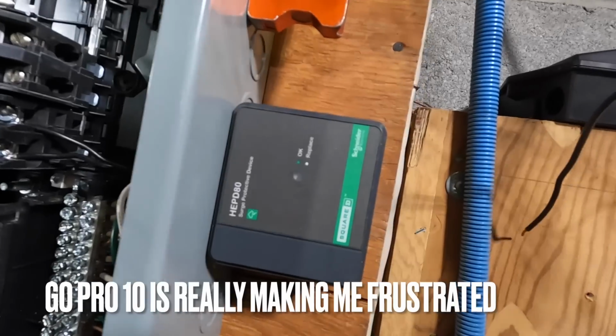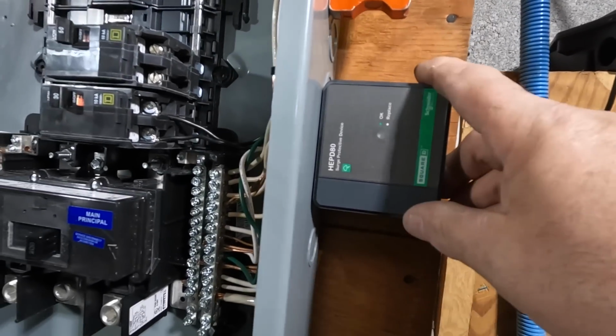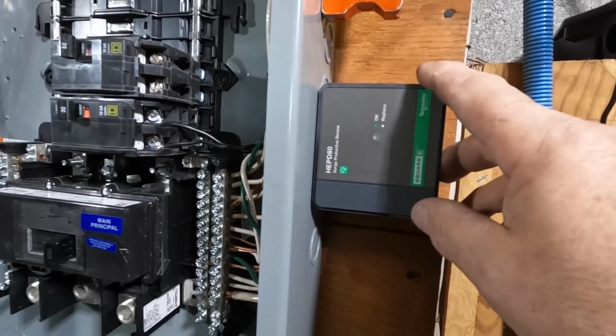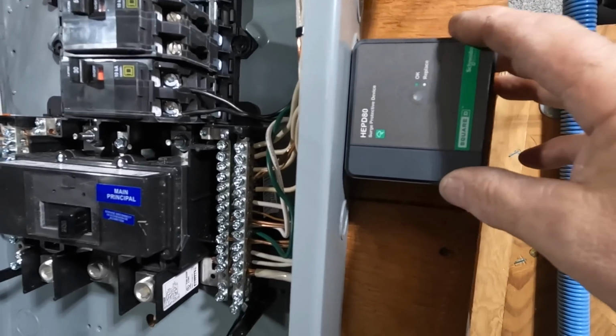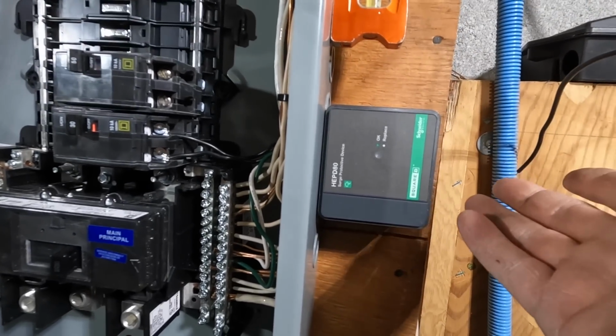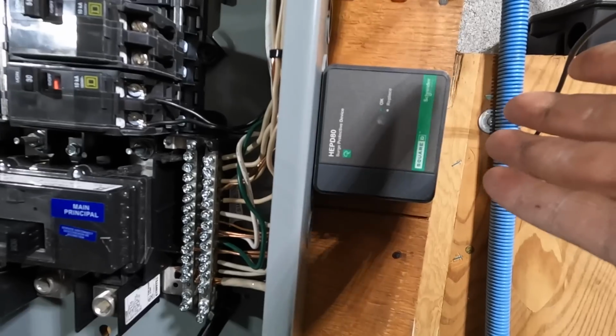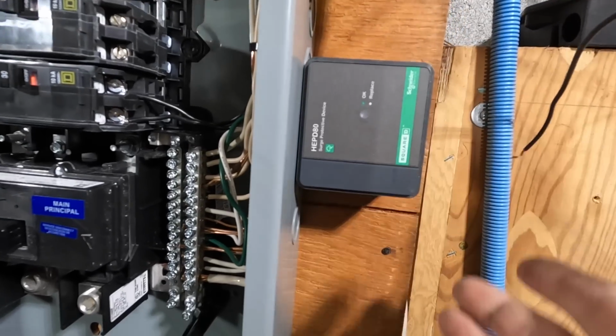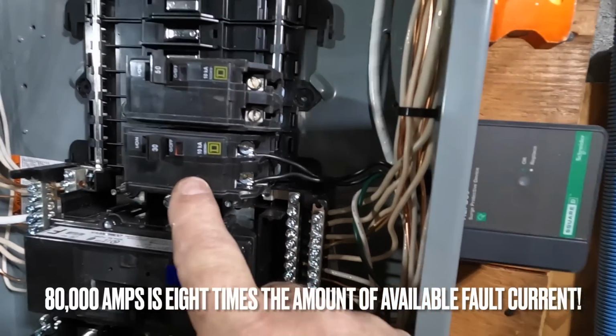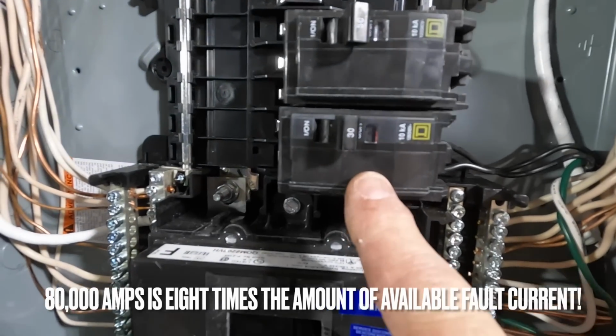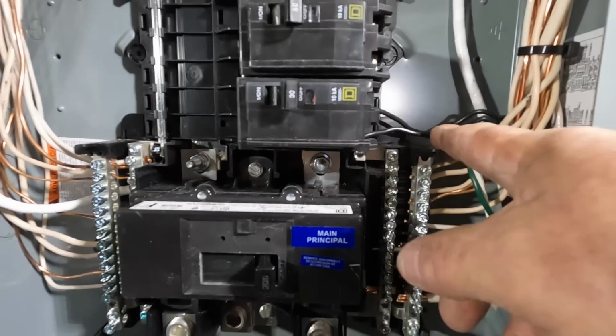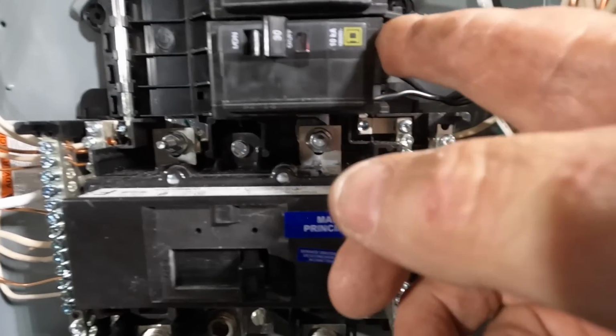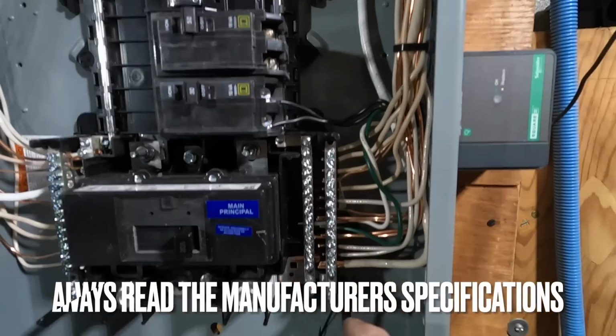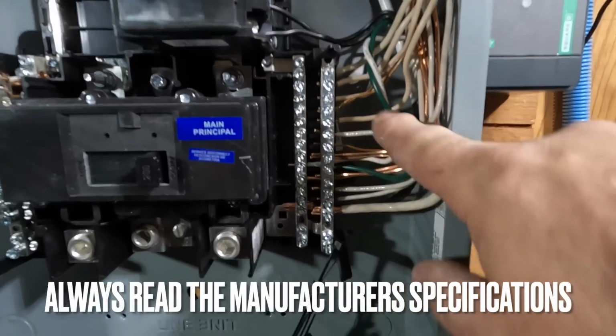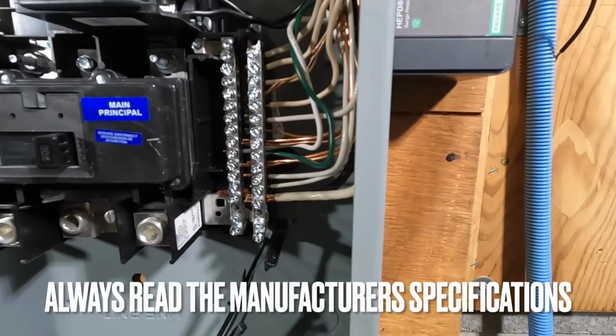So what I did was I added this whole house surge protection device. This is the 80 kiloamp version. This is the joule rating. I'm not exactly sure of this, but this is like the highest rated, best surge protection Square D QO offers. I guess you could hook this up to Homeline as well. And the manufacturer suggests that we connect it to a double pole 30 amp breaker, and have these feeders from the surge protection to the circuit breaker as short as possible. So that's why we have the surge here and the breaker there. And then of course we have our grounds and neutrals connected down below over here as well. That's what you missed.